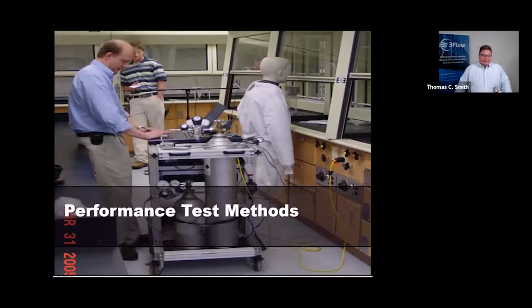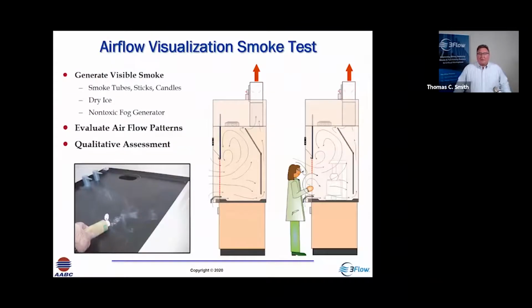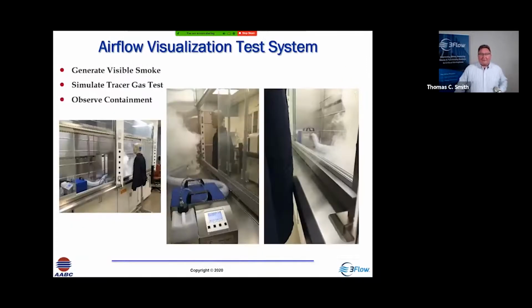Now we move to the next section, which is the performance tests. When we look at performance tests, we're talking about airflow visualization first. We want to generate a visible smoke in the hood, and we want to be able to observe the airflow patterns. We're looking for reverse flow. Is it coming back out of the hood? We're looking at the vortex region in the top of the hood, and how quickly does that material clear out of the hood itself. Now this is qualitative because it's subjective. It's a person looking at these airflow patterns.